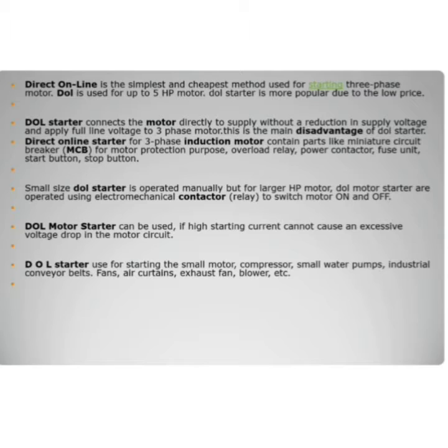DOL starters are used for starting small motors, such as compressors, small water pumps, industrial conveyor belts, fans, air curtains, exhaust fans, cooling towers, etc. Besides, the DOL starter draws a high starting current, a current peak that can rise up to 14 times the rated current of the motor.